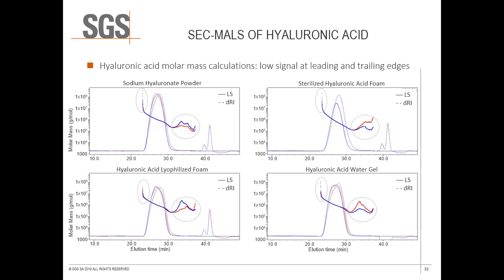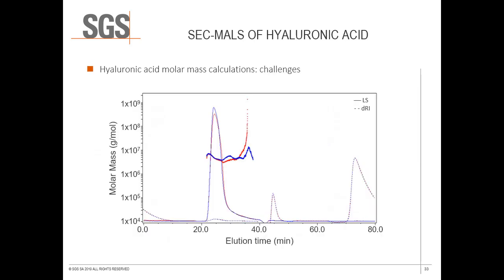Part of the challenge in method optimization is that further diluting the sample decreases refractive index response, and the results are subject to wander, drift, and noise in the baseline of the RI detector to a greater degree. For example, a hyaluronic acid sample which poses much more difficulty may produce a chromatogram more like this, which is a sample from a separate analysis where the hyaluronic acid was supplied in an undisclosed dilute buffer solution, unknown to us in both composition and concentration.